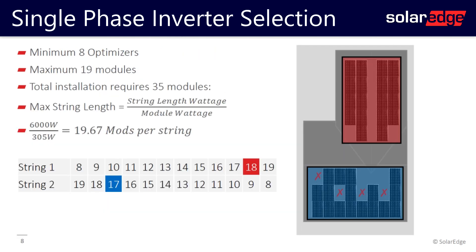You always want to consider how the modules are going to get strung to the inverter. With 35 modules, to find the maximum string length I take the maximum power per string — 6,000 watts — divide by the module wattage of 305 watts, and I find 19 modules per string. The east-west arrays each have nine modules for a total of 18, so I can put 18 modules on a single string. The south-facing array is 17 modules, so that goes on a single string.